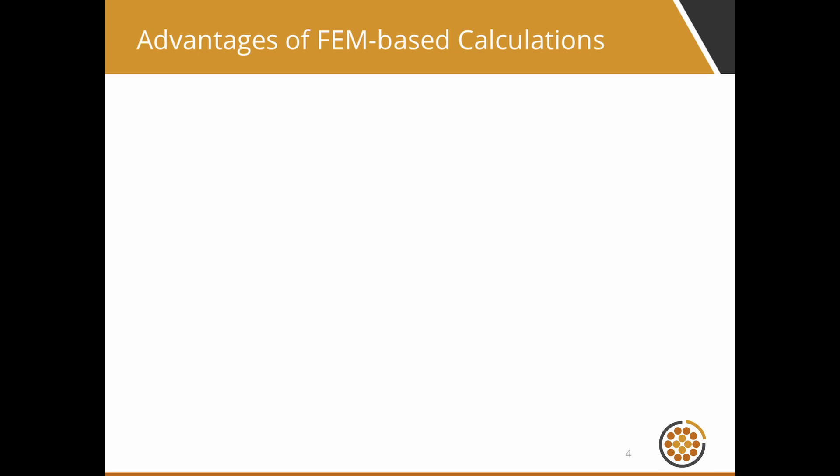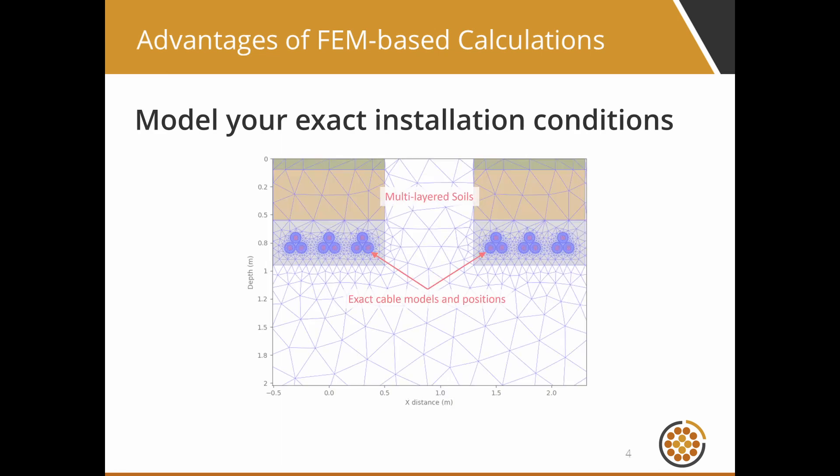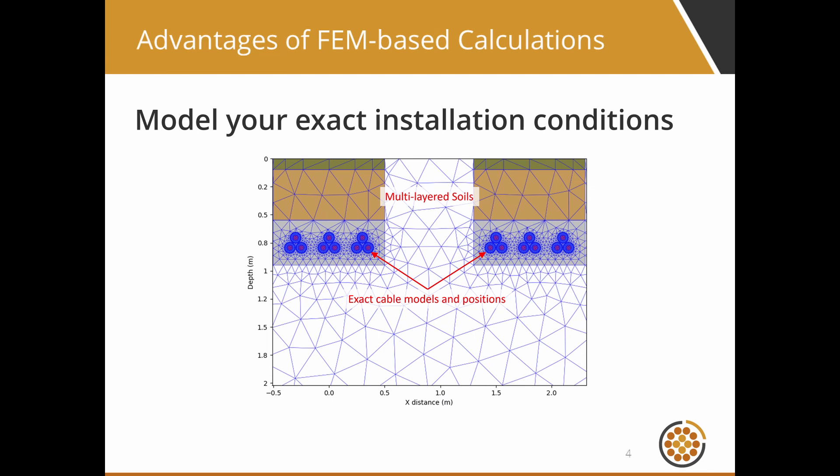There are several advantages to FEM-based cable rating calculations. Firstly, any high-voltage cable installation and configuration can be modelled. Your exact installation conditions can be modelled, which leads to better accuracy. For example, with FEM you can model multiple zones of varying soil thermal resistivity.